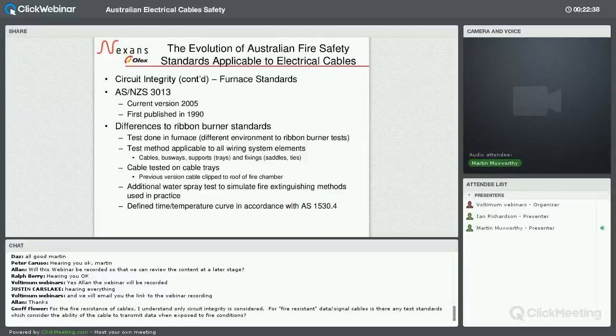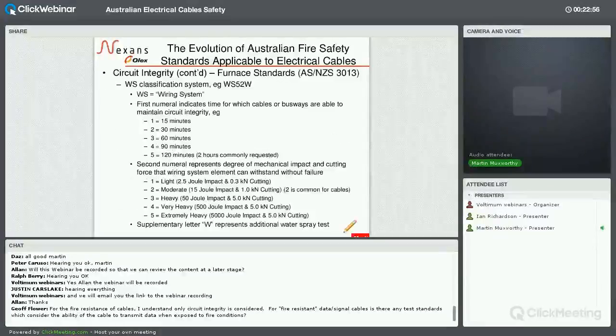And the other thing is, I talked about the validation of the IEC 60331 standard. In this particular furnace standard test, it is done according to a defined time and temperature curve, and this is specified in AS 1530 Part 4. I know there's lots of standards that I've been mentioning, but hopefully it all makes sense.